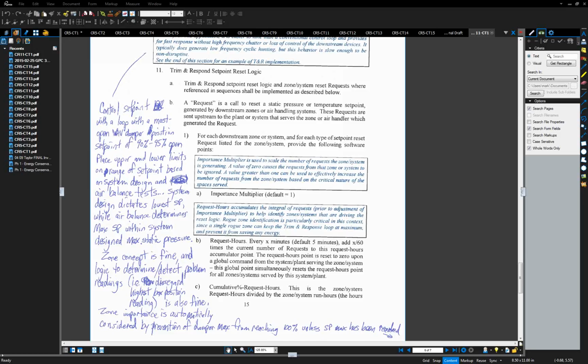And then the other thing is, if you've got a rogue zone, so let's say you've got a VAV box serving a small office or a classroom, and somebody goes in and throws in a bunch of servers in there, and that zone doesn't have enough air to satisfy the load. You don't want it driving the entire building all the time. So one of the things we look at under item B is request hours. We track the request hours, which is the number of requests from each zone times a time interval, and you accumulate that, and then on the EMCS screens you display it, and you can quickly see the zones that have very high request hours. You can alarm on those and put them on a maintenance alarm, and then the facility guys know which zones are having problems.